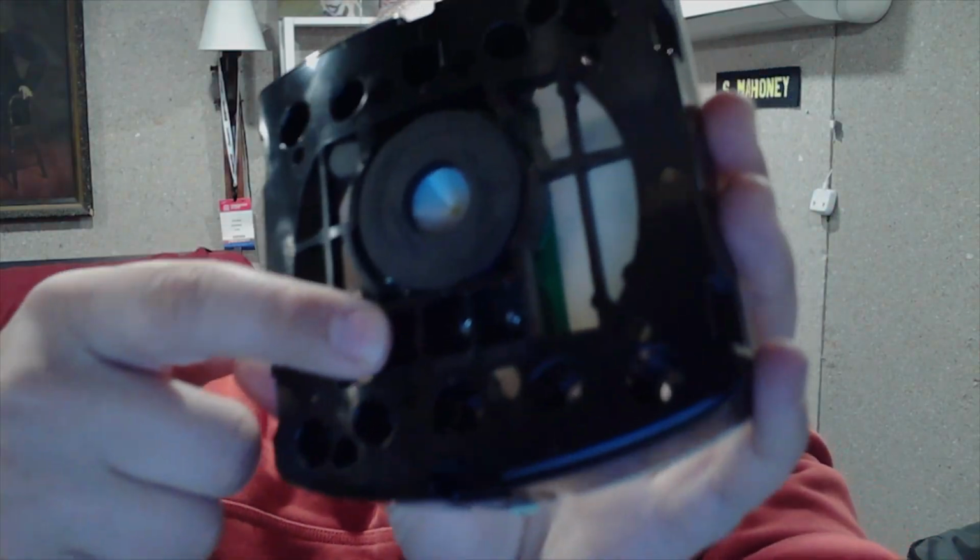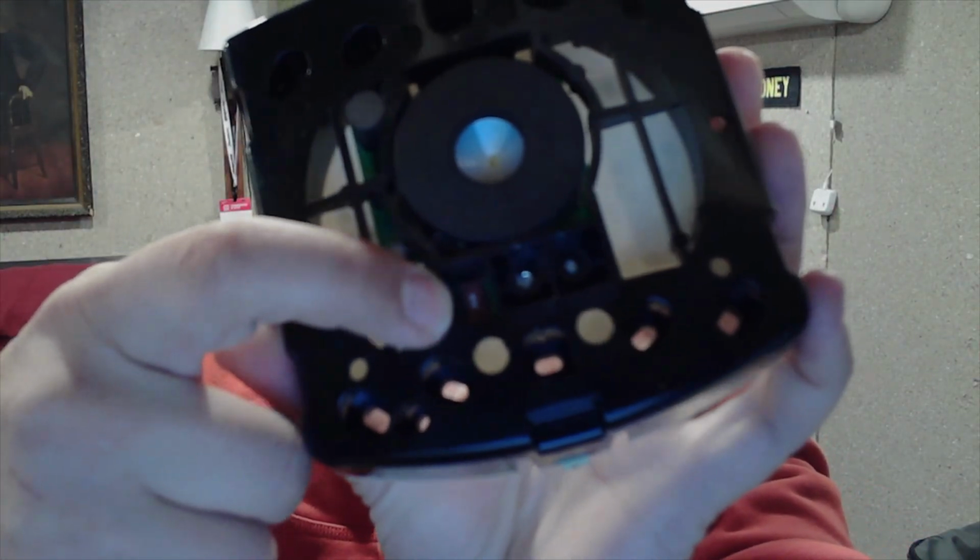And one thing to pay attention to when installing these devices: a lot of audible notification appliances, and this is the example of a speaker here, have the ability to have different levels for wattage or output. This has a little dip switch on the front. It's kind of hard to see right there, but you can see that. You can go either high setting or low setting there. So make sure that these get installed correctly on the right setting for whatever the designer intended for the placement of these to get that proper sound level in the area.